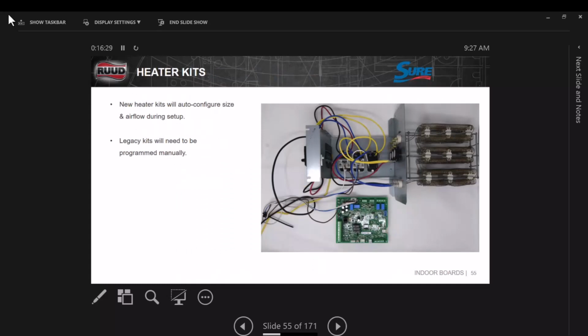Heat kits, the new heat kits will auto-configure their size and airflow during setup. So if you had a Bluetooth unit and you had the correct heat kit in here, the B, then once you plug it in and turn it on, it's going to automatically recognize what it is and what the airflow needs to be to go through it.